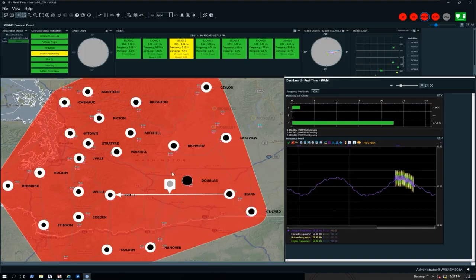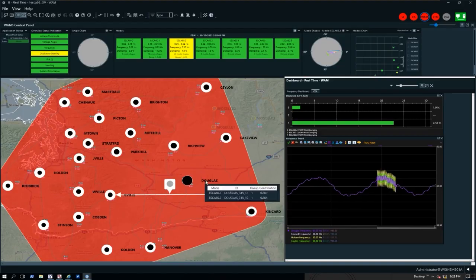I can also change my display mode to show the source locations. And you can see that we're pinpointing the fact that Douglas has the largest fill in this instance. And so Douglas has been identified by WAMS as being the source of this oscillation. So some of the things that you might do as an operator when you see oscillations on your grid and they've been identified in the power plant that's associated, you might determine that there's some kind of a mechanical issue with that plant. So it might be that the power system stabilizer has issues. It might be in a poor operating mode where it's unstable.